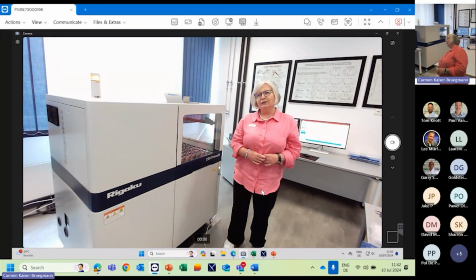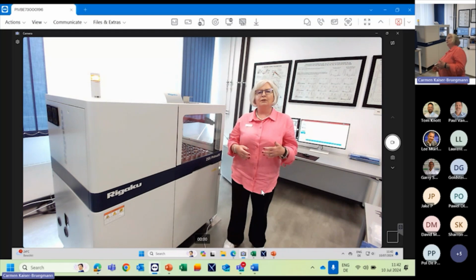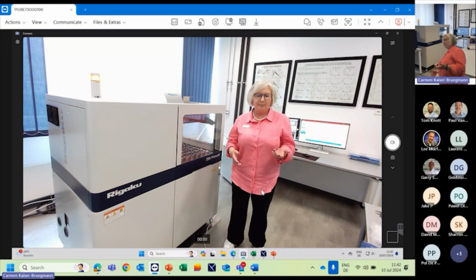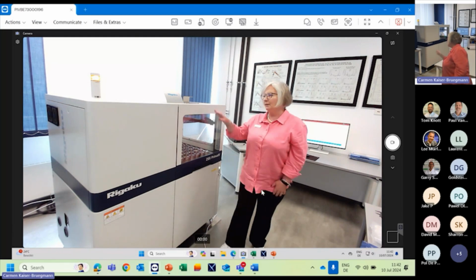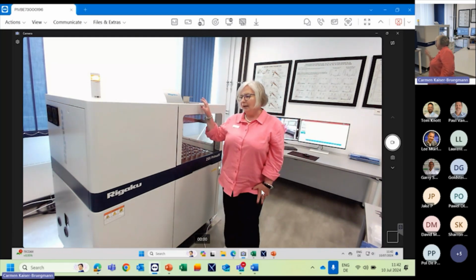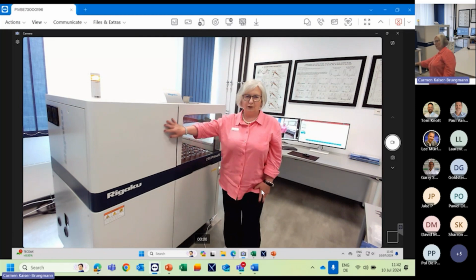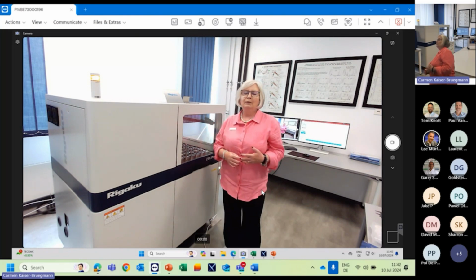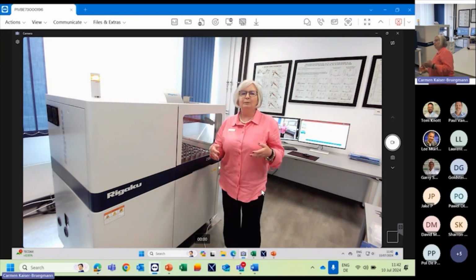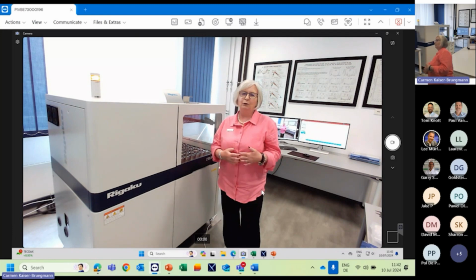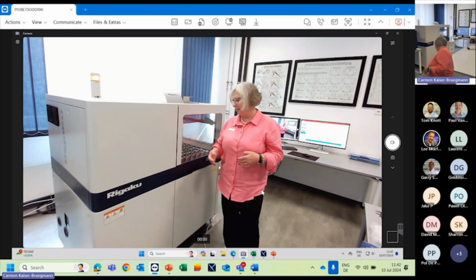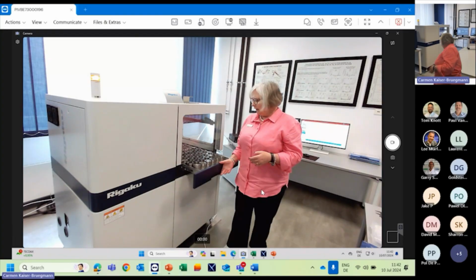We can also tell you a lot about the instrument in terms of its instrumental conditions and parameters. But one of the most beneficial things for you is that this WDXRF has an X-ray tube above your sample. This is a big advantage because we do not have any broken samples or dust falling on top of our X-ray tube, which usually can be a problem for industrial customers.